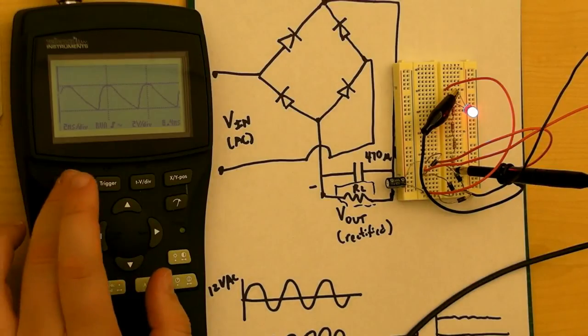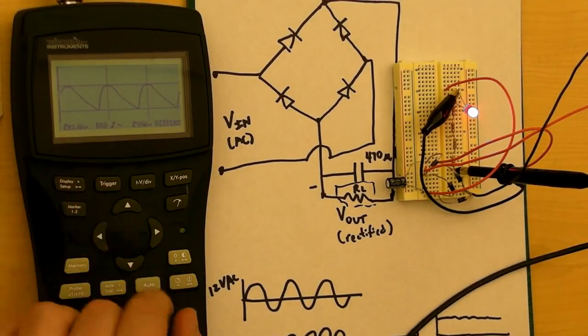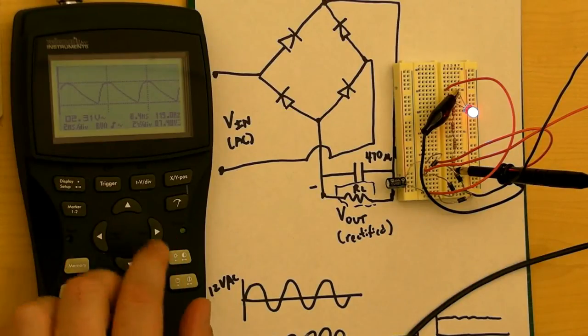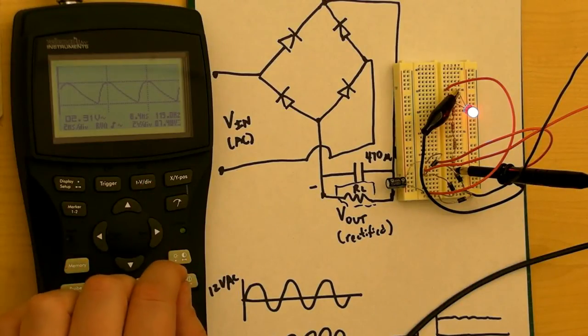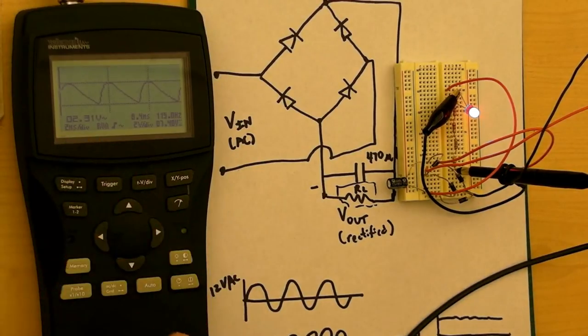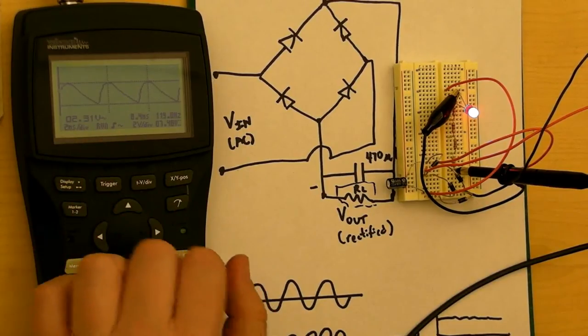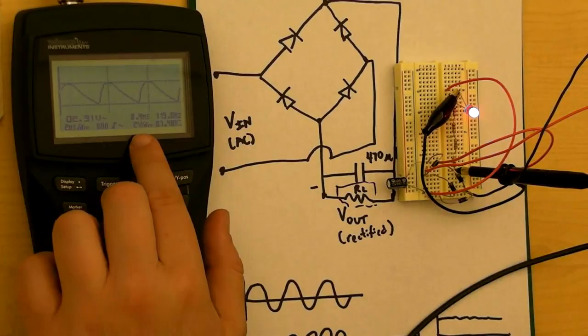Now I'm actually going to switch to a different display mode. You can do that by pushing display and then hitting the right and left arrows. It's kind of useful. It shows you a lot more information here. It's showing that it looks here like I'm getting 2.3 volts ripple in the things, what I was reporting, so I was wrong before.